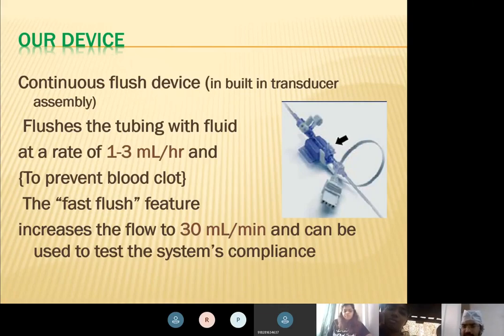That means 1 ml per hour does go in anyway. So in a full day, 24 ml is going to go in. So if you keep on opening it up and down, when you open it, the fast flush feature will increase the flow to 30 ml per minute. That means if you pull the transducer up for 1 minute, 30 ml will go inside. If you do this 10 times, 300 ml will go inside. You understand? If you do it for 10 minutes, 300 ml will go inside.